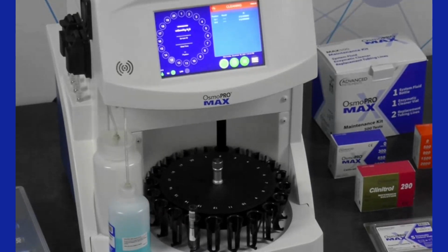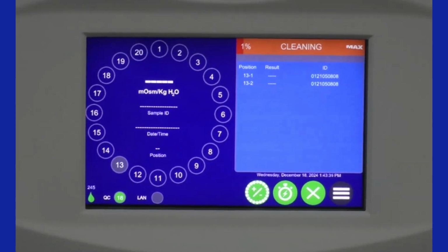And then going back to the software, you can actually see where it's scanned in the tube that I had loaded up in position 13. Again, it doesn't really matter where you put it. And there's a 13-1 and a 13-2. And that's because, remember, I had it pre-programmed to run each test in duplicate. So that 13-1 will be the first result. That 13-2 will be the second result. And the ID, which will likely be the accession number that you use as a patient identifier in your hospital, will be located over to the right side with the result in the middle.